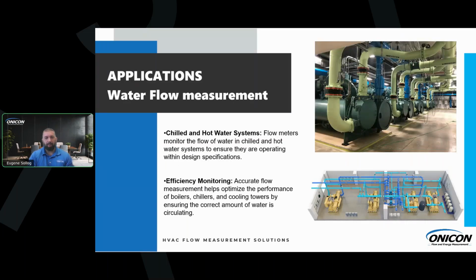For water flow measurement, maybe you're not doing BTU and you're just measuring right off of a chiller, but there's no room. Like in this picture below, it's coming right out of a chiller to a 90 into one of our flow meters, and it goes right into a pump header. And then after the header, it splits into 10 different directions. To get within the straight run requirements to measure accurately, the inline mag is the ideal choice for those tight spaces.